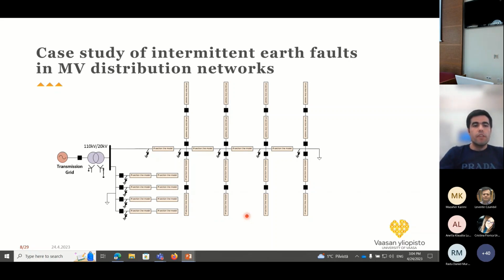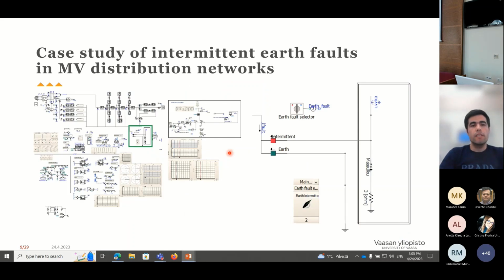To study this phenomenon, we are studying a real network in Finland known as the Sundom Smart Grid, which is 110 to 20 kilovolt, and we are capturing real data in this network. But we haven't used this data up to now because, as I mentioned, we started studying intermittent earth fault just 3 months ago. We are considering lots of scenarios, different faults in different locations, and we also modeled this network in PSCAD software. In this part, we modeled both intermittent and earth fault, which is shown clearly here.